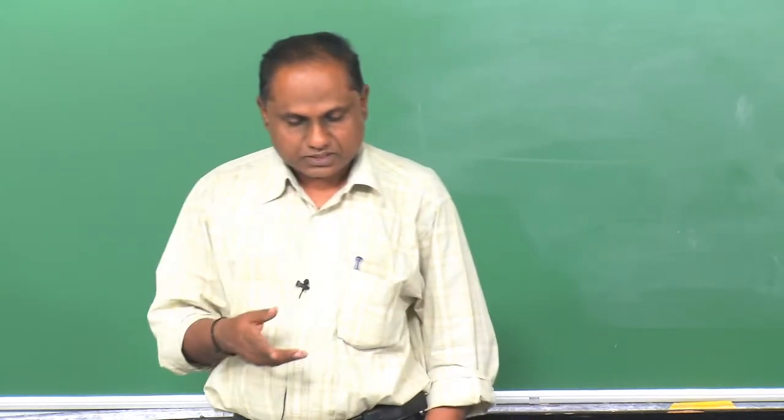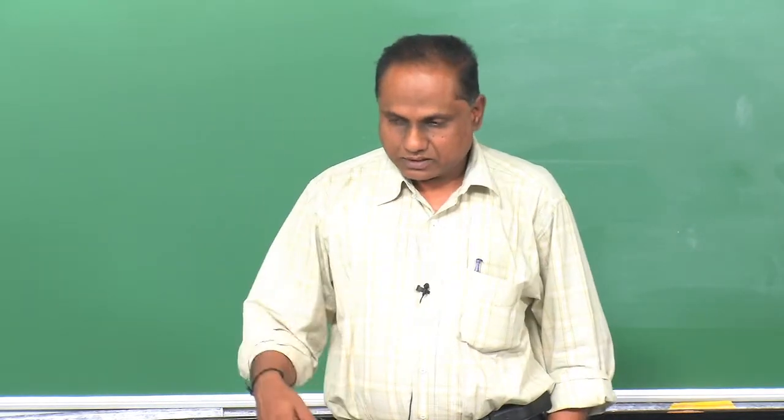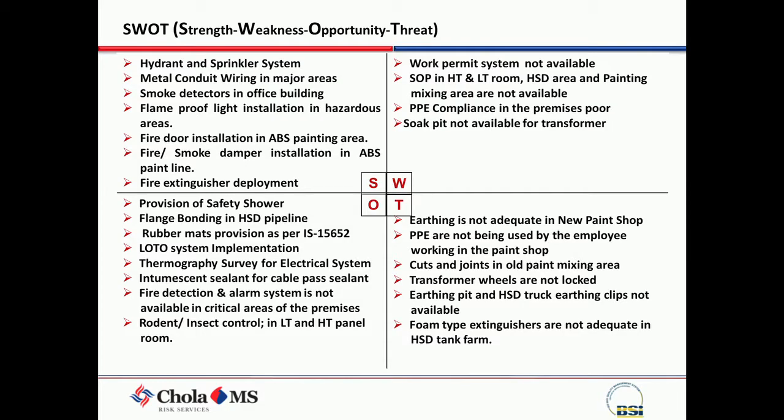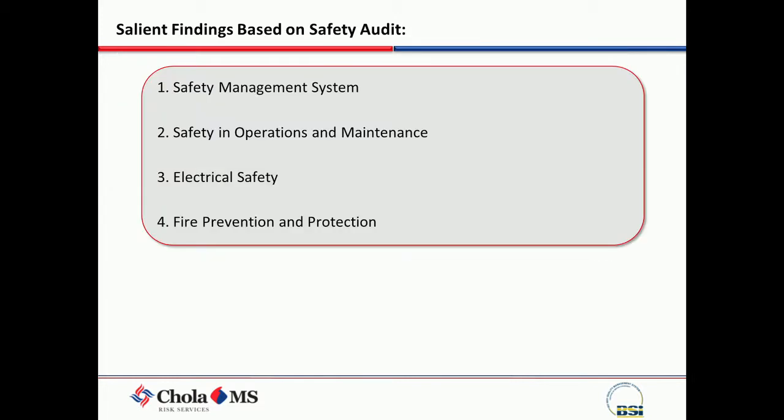Then this transformer wheels, I will just show you the photograph. Earth pits and HSD tank. Earth pits were not available, I think. Then foam extinguishers. I told you when you're handling HSD or this type of solvents, you need to have foam type extinguishers. So these are some of those.